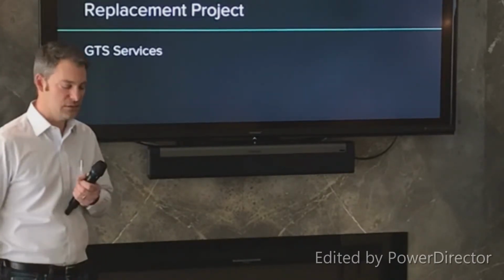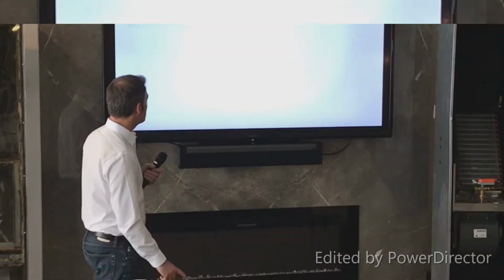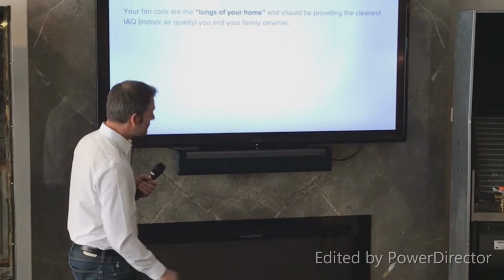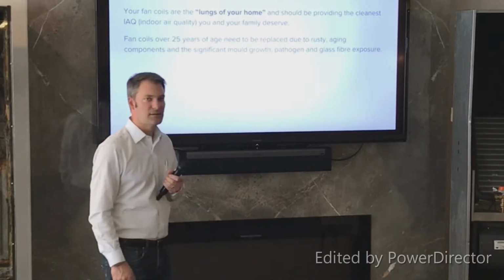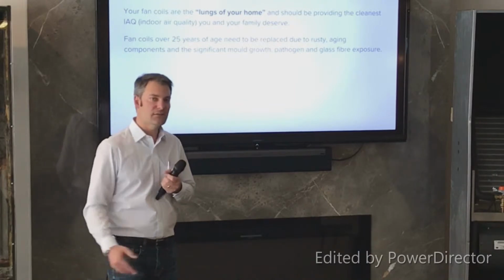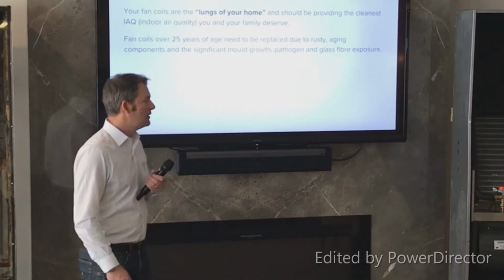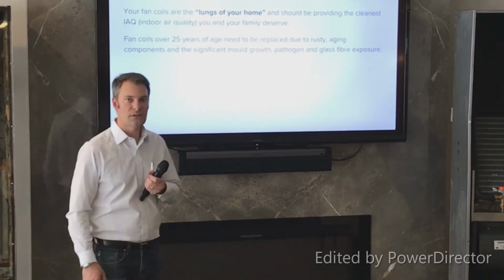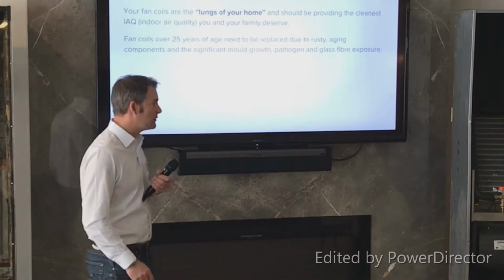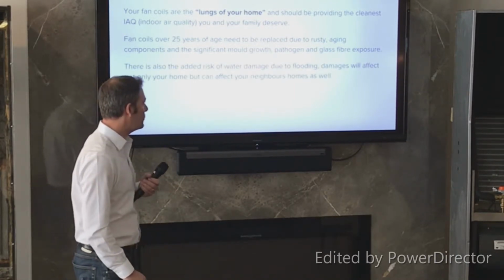Today I'll be speaking to you about fan coil replacement for condo buildings. So in this building in particular, we've got 27-year-old fan coils that we believe have sort of passed their expiry date. The reasons we believe this is because of the mold growth that's occurring inside the cabinets, as well as the rusting drain pans, the other older components that are breaking down like actuators and motors and thermostats, and exposed fiberglass inside the fan coil.